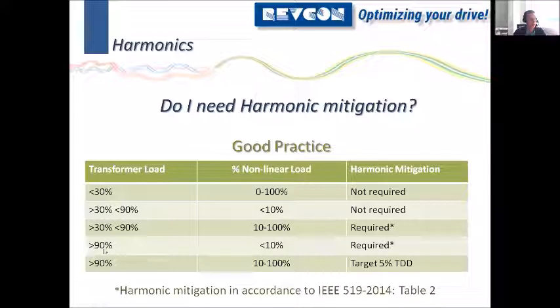If you have more than 90% load on the transformer, no matter how big the drive load is, you should always make the same calculation, above 90%. And if you are above 90% and you know the drive load is above 10%, just target 5% TDD. That should be, then you should be okay. Because if you're above 90%, you don't have the margin on the transformer to do anything above 5% anyway.